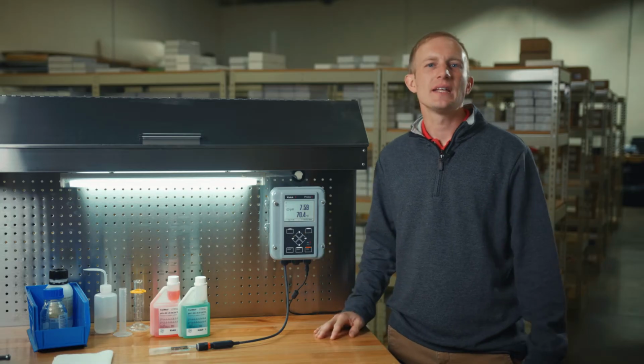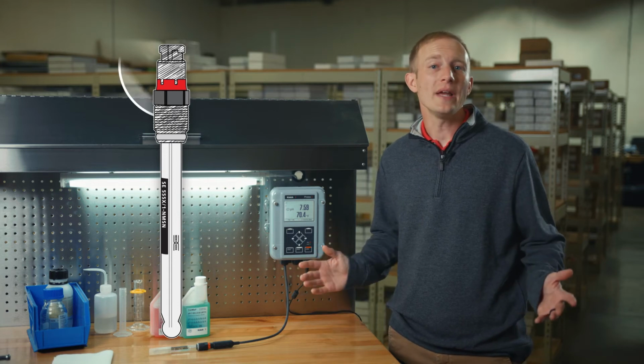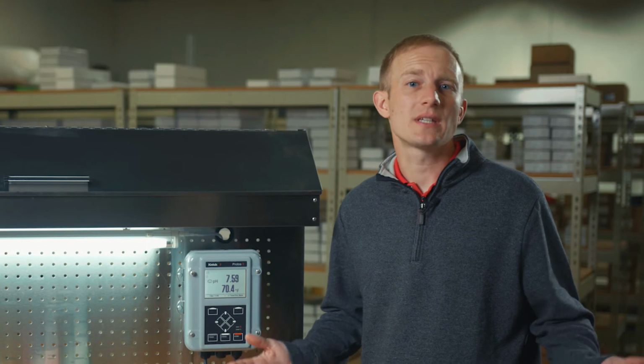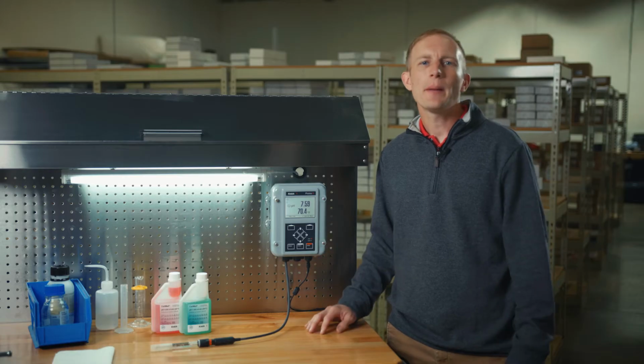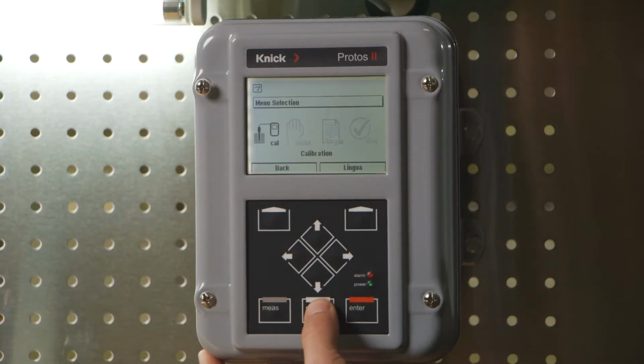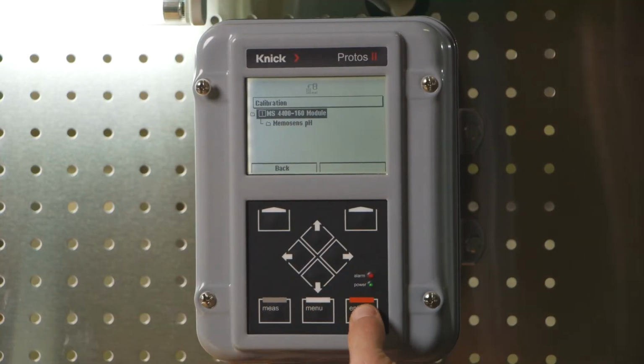As our connected sensor is a Memosens smart digital sensor, the calibration will be written and stored in the head of the sensor. However, these same steps can be utilized when performing a calibration in the field. Let's begin by pressing Menu on the main screen and then Enter on the calibration menu.